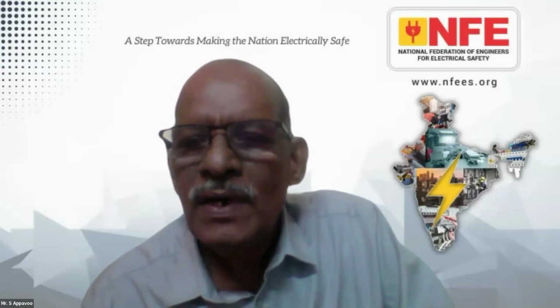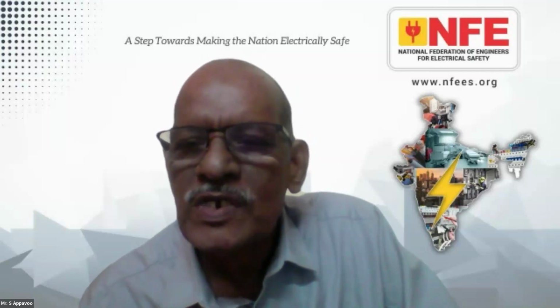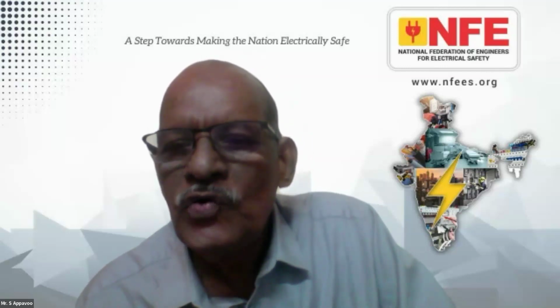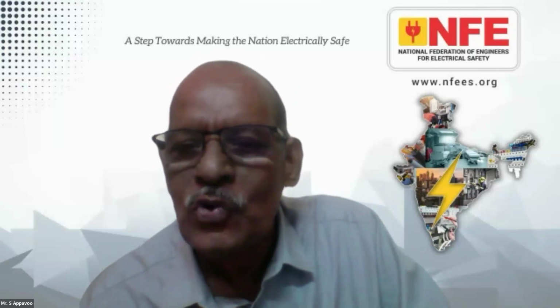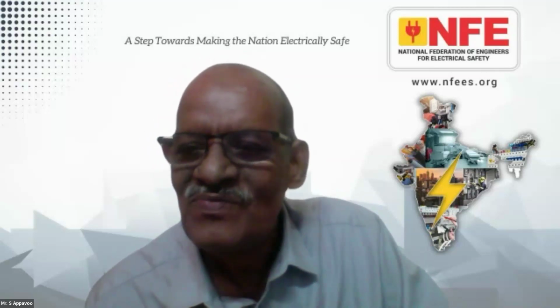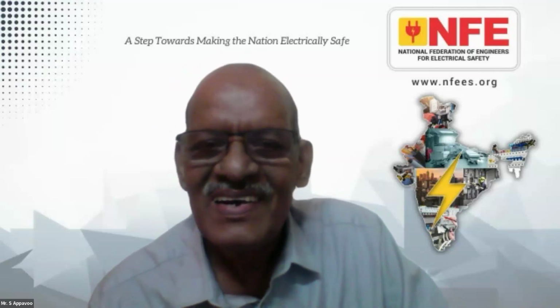Okay. Then another question from Govind Jha. How do we know whether the harmonics issue is coming from the source or from the building system? In 90% of cases it will definitely come from the load only, whatever the load is. For that you need to do an analysis of the harmonics. You have to conduct a harmonics analysis for the system, and then only you will be able to understand that. But in 90% of cases it will come from the load only.